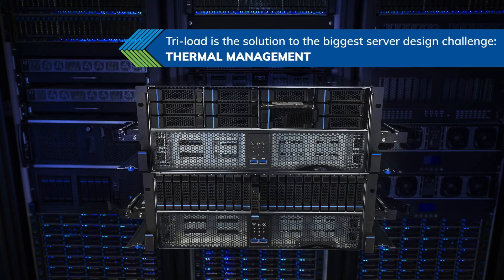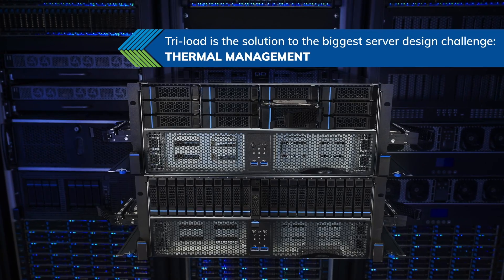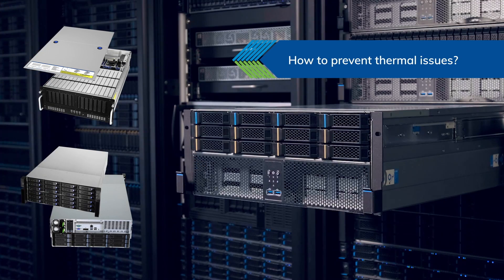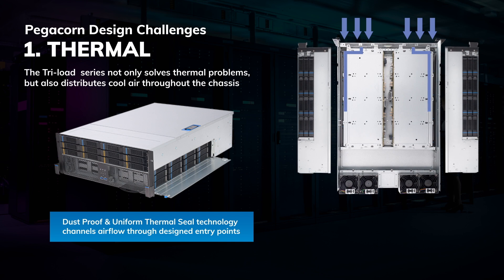Tri-load is the solution to the biggest server design challenge: thermal management. In 4U cabinets, the HDDs are usually mounted on the front and rear sides, resulting in preheating problems. The actual airflow entering the server is crucial regardless of cooling measures in the data center.